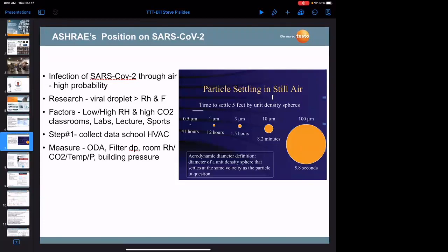Good question. Let's talk about ASHRAE first, the document. I've been working to ASHRAE guidelines from their manuals for decades, and everything in an ASHRAE manual is engineering guidelines. When mechanical engineers design around the capacity of a mechanical rooftop system, they look at the environmental values or weather data placed in the ASHRAE manual. They use that to help design the capacity of that built-up unit. None of those are code, but engineers still adhere to them as design guidelines.